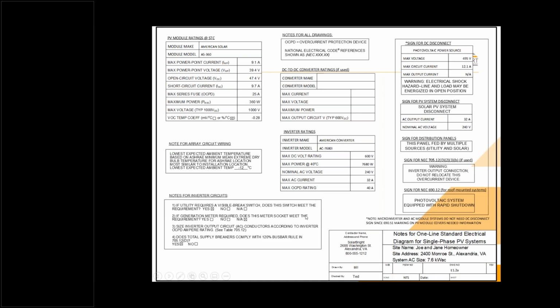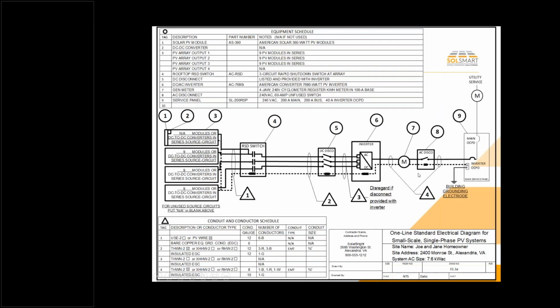All right. There's also information here about a visible break switch, and so many, if not all, of the utilities in Virginia require a visible break switch. This is just like a knife blade switch, similar to what you'd have on an air conditioner, and that's got to be located typically near the meter is what they generally require. And so we have that in the plan. Let's just review that. That's this little disconnect over here.